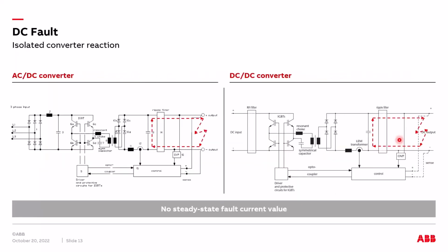If we have a so-called isolated converter, this means that inside our converter we have a transformer in order to guarantee the galvanic isolation of the system. As you can see, if we have a fault on a DC side in a AC-DC converter, or on the output of a DC-DC converter, imagine for example that the output is our local DC microgrid, so our local DC distribution, we can avoid the contribution from the AC side, for example on the left, for the steady state contribution, but we still have the DC capacitor discharge current in both configurations, AC-DC converter or DC-DC converter. What does it mean? It means that we still have to install on the DC side suitable protective devices in order to be able to detect and interrupt this short circuit contribution coming from the DC capacitor discharge.